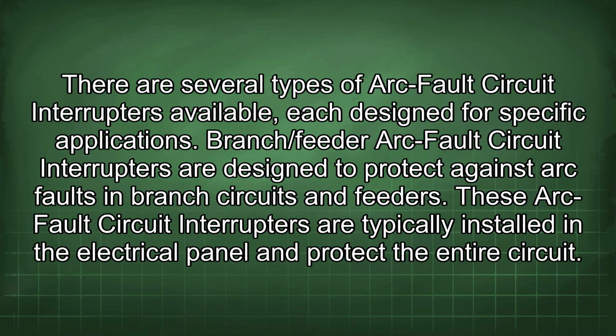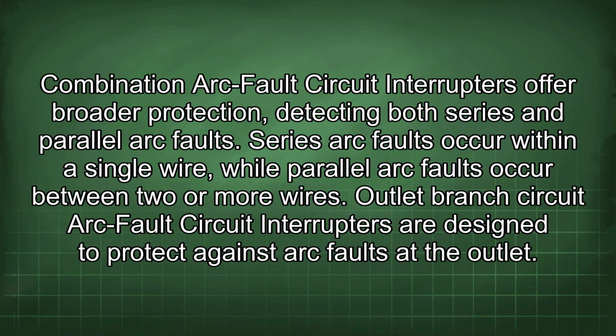There are several types of arc fault circuit interrupters available, each designed for specific applications. Branch/feeder arc fault circuit interrupters are designed to protect against arc faults in branch circuits and feeders. These are typically installed in the electrical panel and protect the entire circuit. Combination arc fault circuit interrupters offer broader protection, detecting both series and parallel arc faults. Series arc faults occur within a single wire, while parallel arc faults occur between two or more wires.